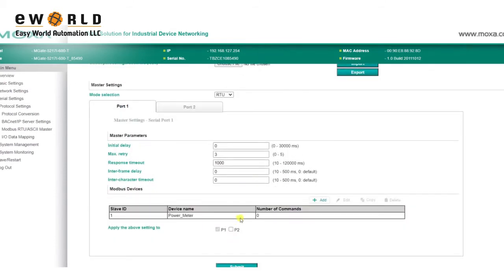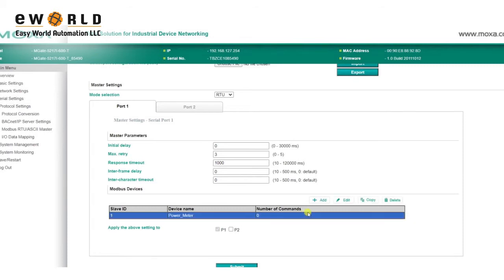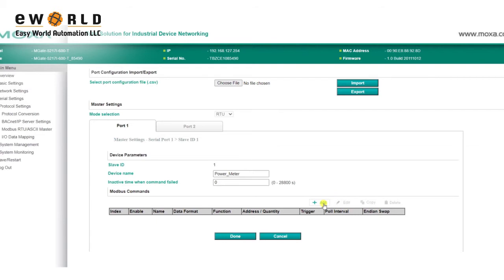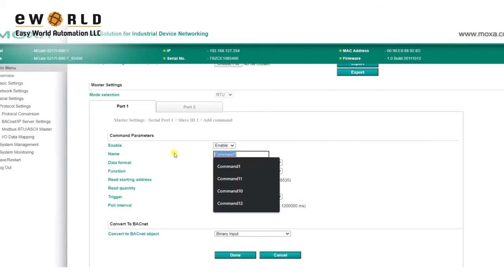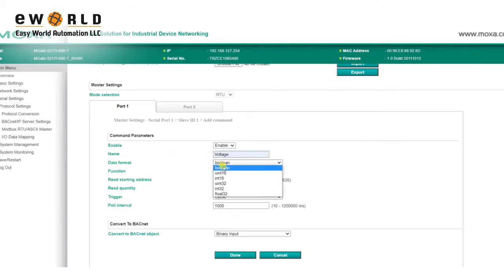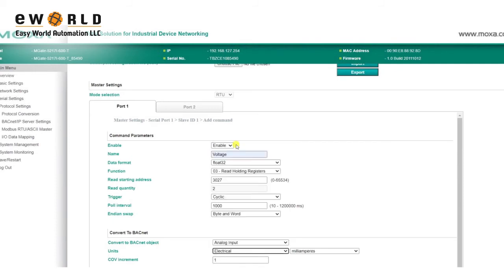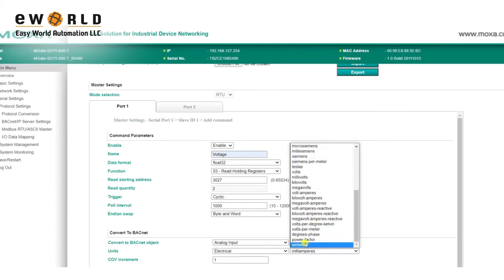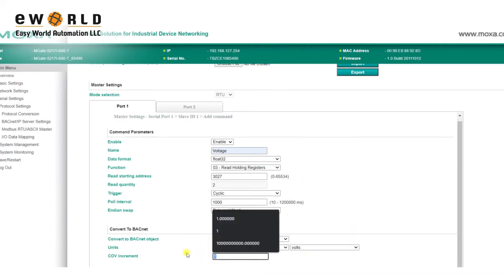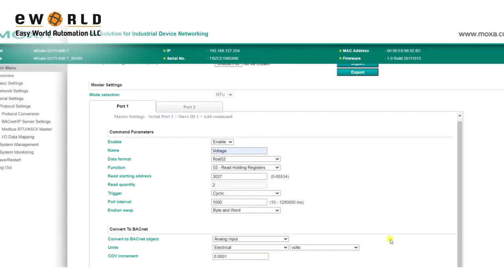Now we're going to add Modbus commands so we can get voltage and frequency data. To do so, we select our power meter, click Edit, then click Add to add the command. Enter the command details, such as the name, data format, function code, read starting address, and Endian swap. Choose the BACnet object type you want to convert to, and set the measuring unit. Here, we're selecting analog input as the object type, and electrical volts as our unit. We'll also set our COV increments, and then finally, we'll click Done.